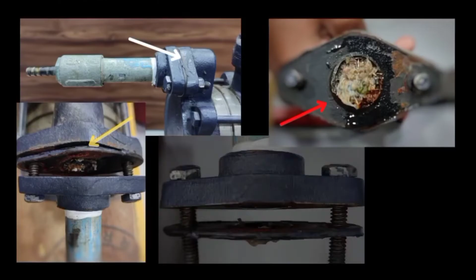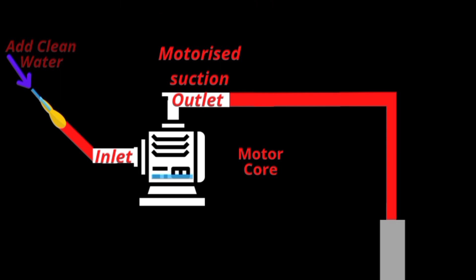Second, loss of suction at the tip, but the motor is still running. This happens because the core of the motor is completely empty of liquid and cannot create vacuum to pull out more liquid. To solve this issue, just put some water into the inlet pipe and your suction pressure will appear again.